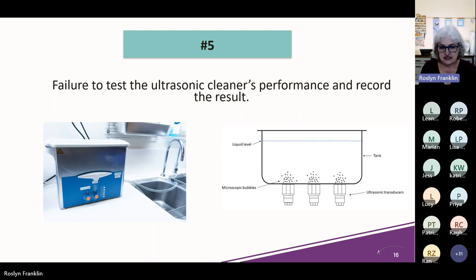So what we want to test is that those transducers are working properly. Many of our machines don't actually have a light or a gauge that says they are working properly. So this is when we do what they call a performance test, where we check its ability to produce these bubbles.